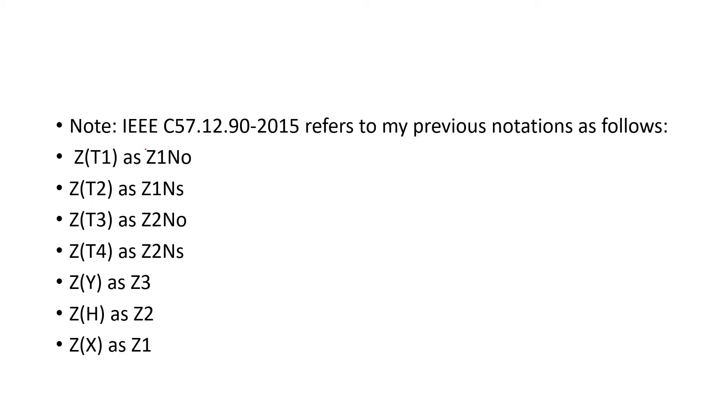So just some notes here: IEEE C57.12.90-2015. So this 12.90 is the test code, and 2015 means it was published or approved in 2015. So what I call zero sequence impedance obtained from test 1, that's what they call it. The same thing here, so they mean the same thing, it's just... So like when I built the T-model, so I called it H, X, called it Y. So if you read IEEE, this might be 1Z3 something like that, but they mean the same thing.